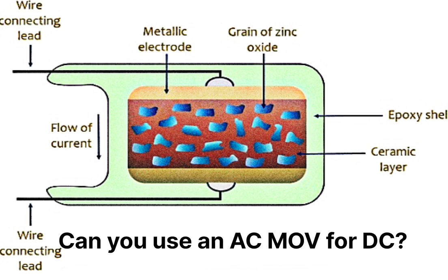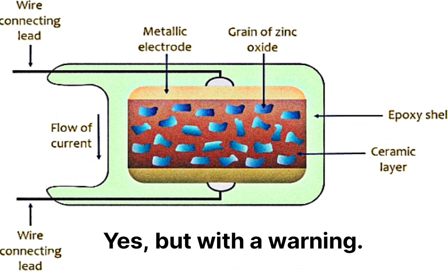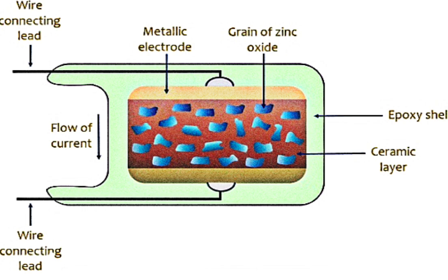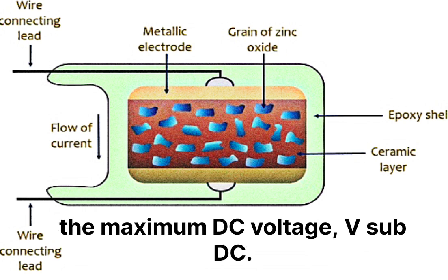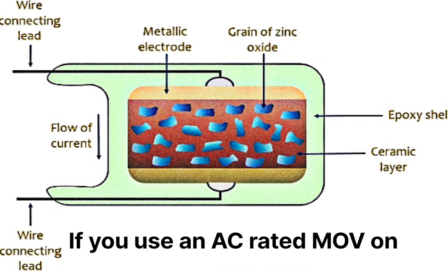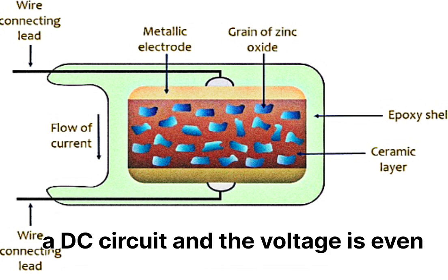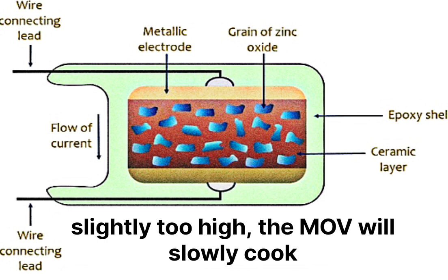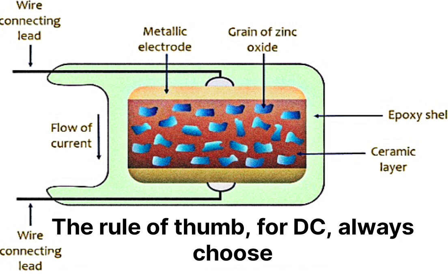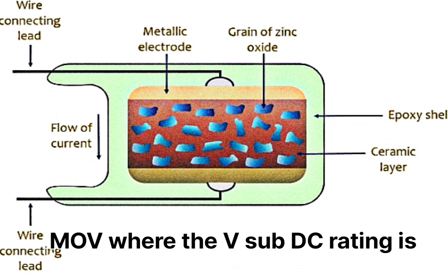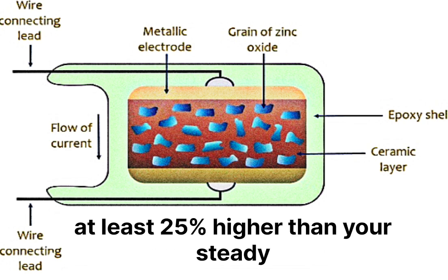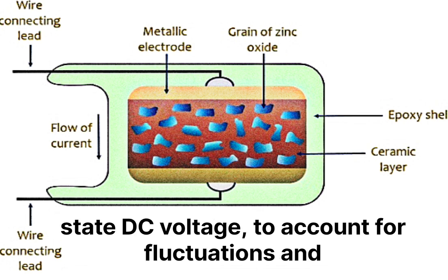Can you use an AC MOV for DC? Yes, but with a warning. You must look at the datasheet for the maximum DC voltage, V sub DC. If you use an AC-rated MOV on a DC circuit and the voltage is even slightly too high, the MOV will slowly cook itself. The rule of thumb: for DC, always choose an MOV where the V sub DC rating is at least 25% higher than your steady-state DC voltage to account for fluctuations and heat.